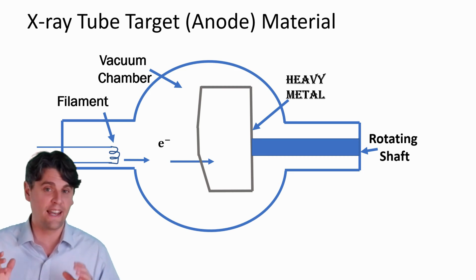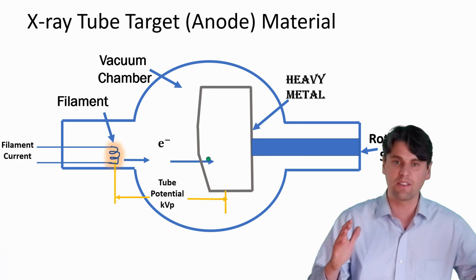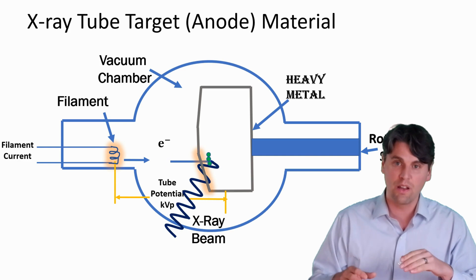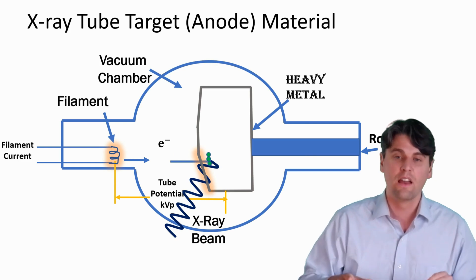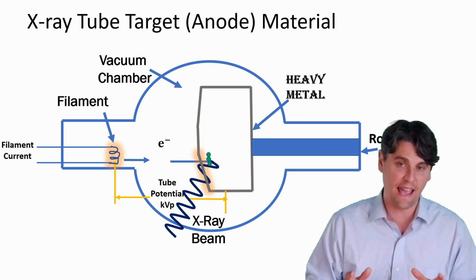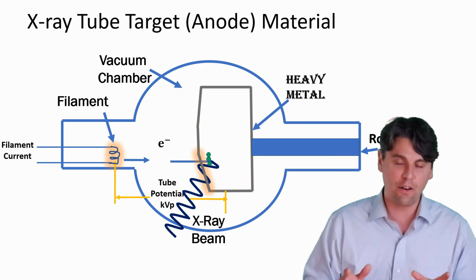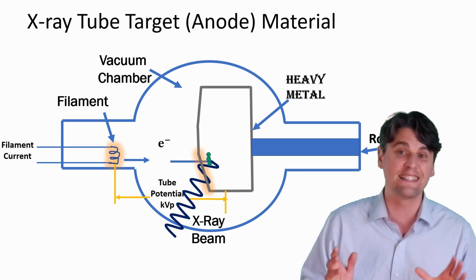Next thing we're going to talk about is the target material and its influence on the beam quality. So if we remember, we have electrons, they come out of a hot filament, and then they're going to get slammed into the anode. They're going to get pulled across by a KVP, and then they're going to get slammed into the anode. As they travel into the anode, they will interact in characteristic and bremsstrahlung interactions, and out come the x-ray photons. Those x-ray photons have to pass through the anode material. Since they have to pass through the anode material on their way out, that anode material is actually going to influence the quality of the beam because some of those x-ray photons are going to get attenuated within the anode material itself.